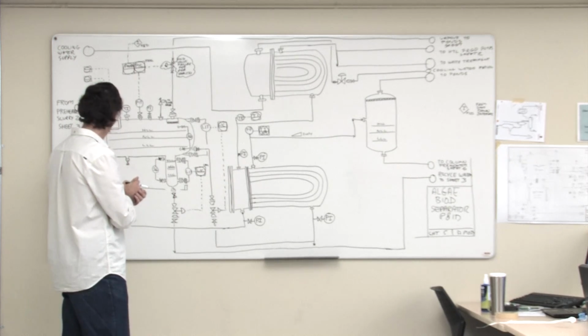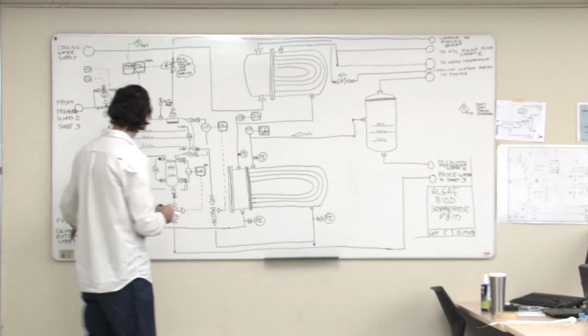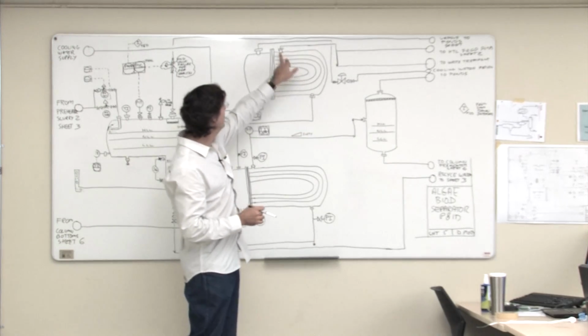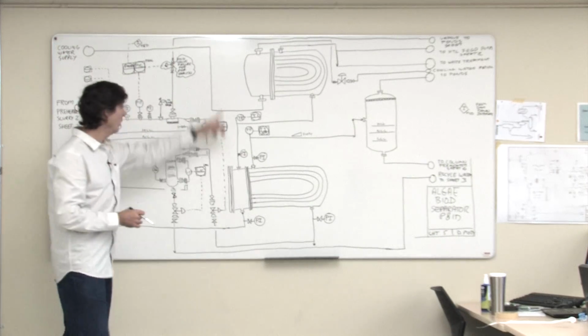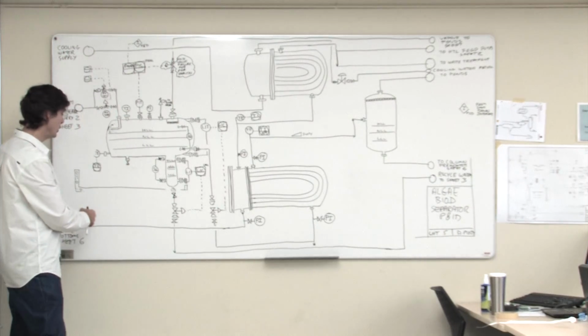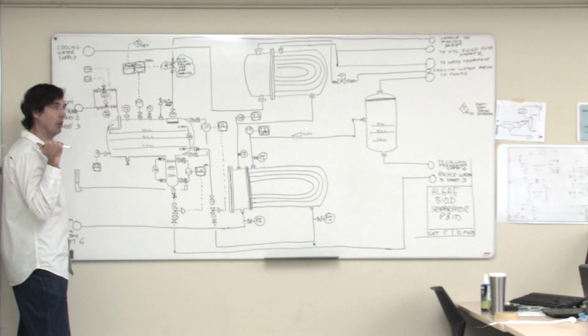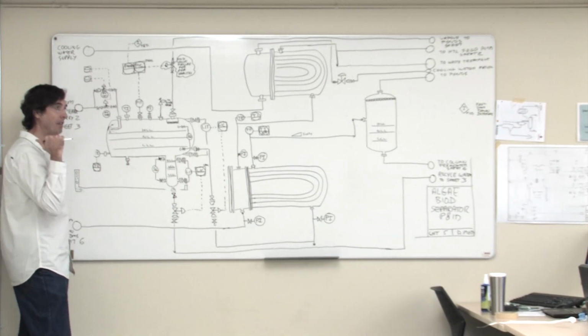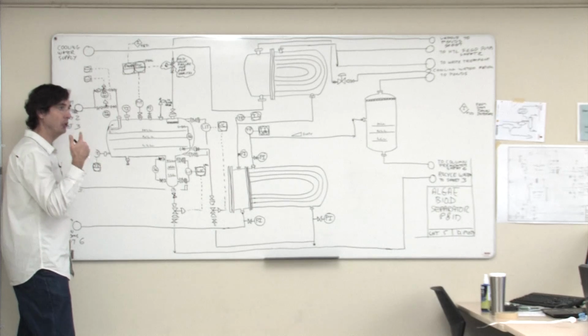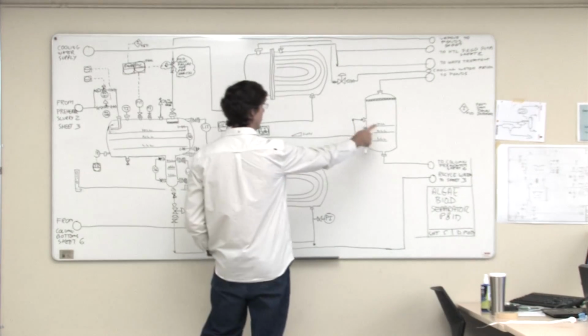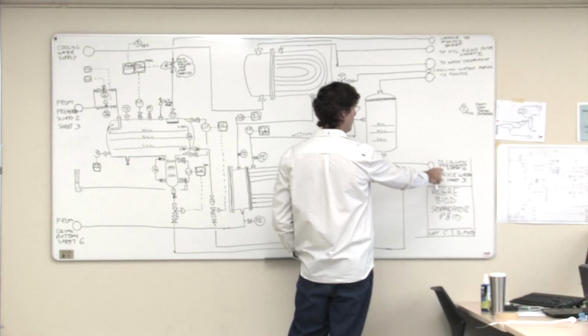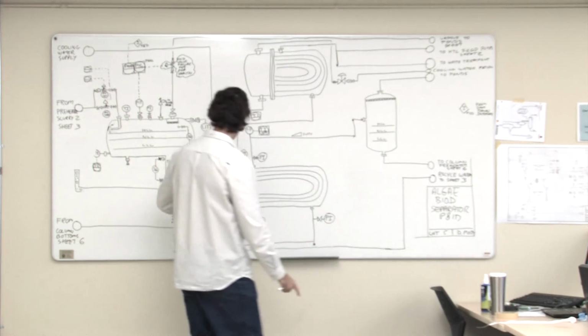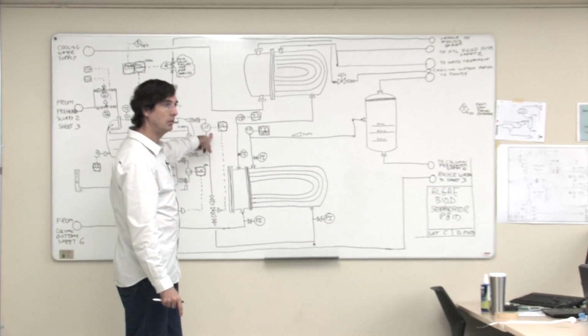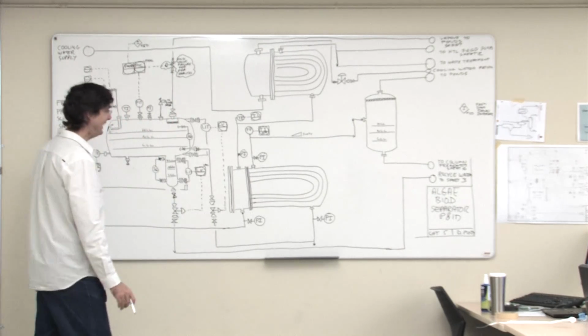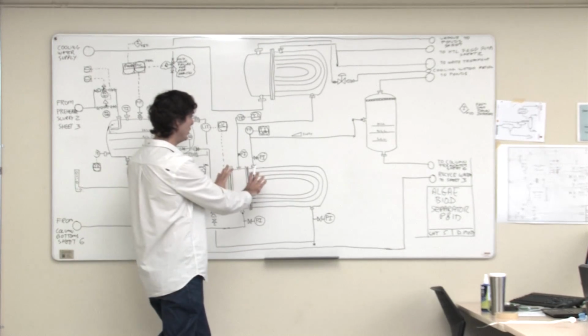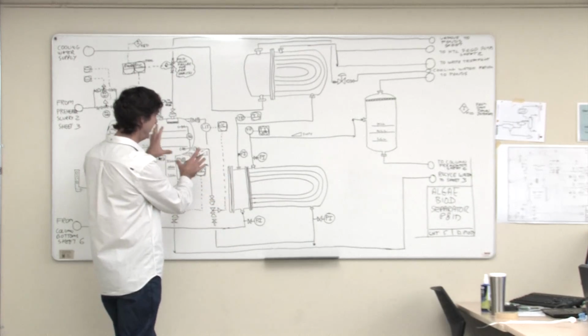Could be. The problem is, this is coming from the column bottoms, right? So if we put a control valve on this line here, we're going to get ourselves into trouble because the column bottoms is going to have level control on it. So if we put a valve here, there's going to be another valve on the column bottoms level, and we're going to have dueling control. We'd be basically fighting that level control. So somehow we need to manipulate the flow through that heat exchanger without manipulating the total flow.